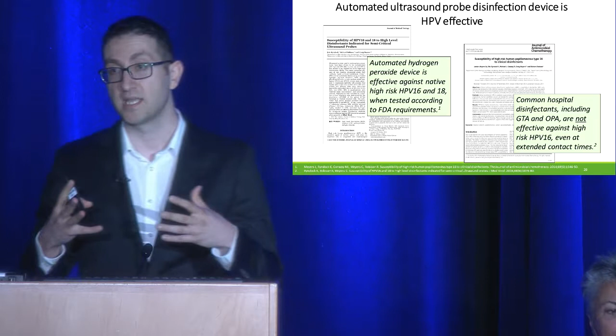So some studies were published comparing high-level disinfection procedures for these probes. And it was clearly identified that an automated hydrogen peroxide device is effective against these native HPVs according to FDA requirements. So it is tested per FDA, which is the key here. Many folks say, well, Roy, it's not only about the disinfection. It's about the entire process: the cleaning, the transportation, the high-level disinfection, the handling, the storage, et cetera. And I get it. That's very true. However, if you just compare the solution itself, we know for a fact that OPA does not kill HPV, and hydrogen peroxide in an automated system does. That's the takeaway.